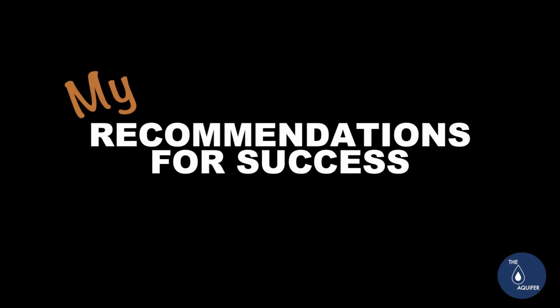So here are a few recommendations that I developed for successful application and operation of one of these backup units. The first one is to make sure the setup is appropriate for the priming capabilities and that NPSH requirements would not unduly surcharge or risk the upstream collection system. Overall, the backup pump is basically equivalent with a generator. The key determining factor between a permanent generator and a permanent pump would be the depth of the pump station and an acceptable water level upstream relative to NPSH.